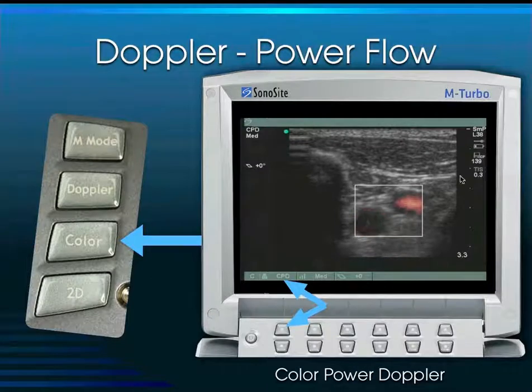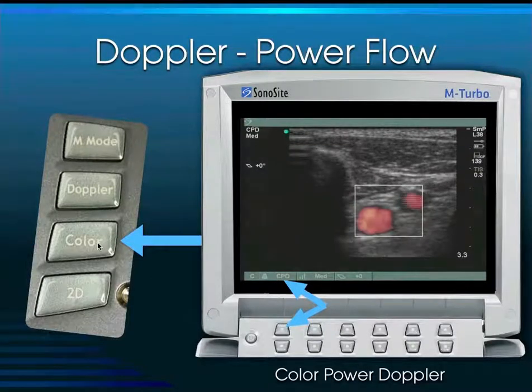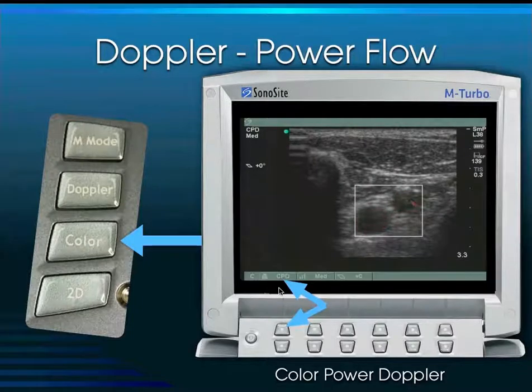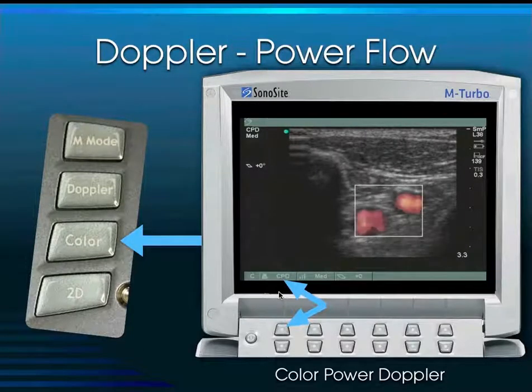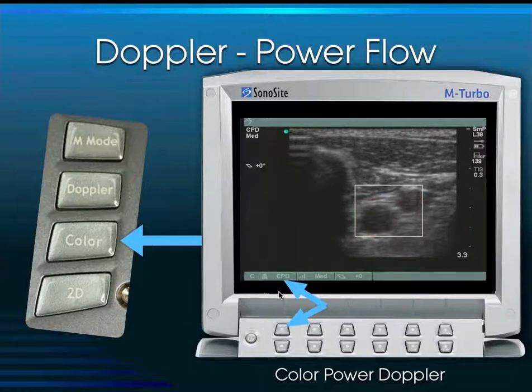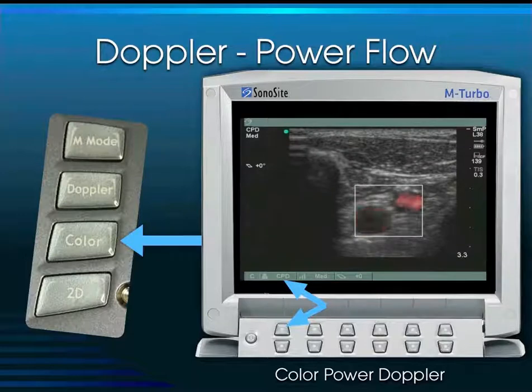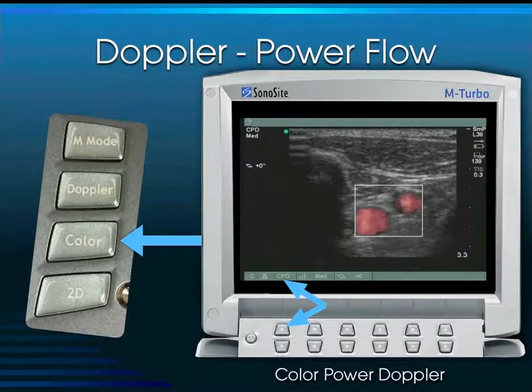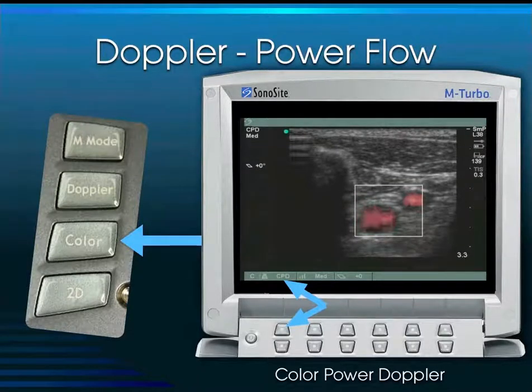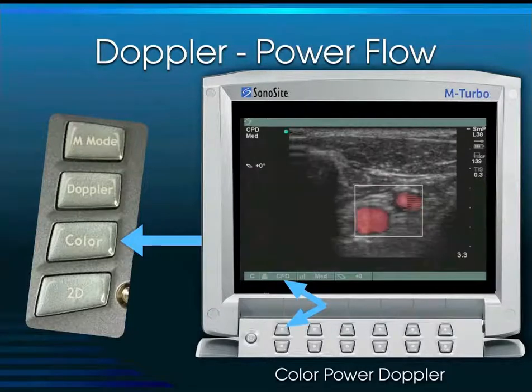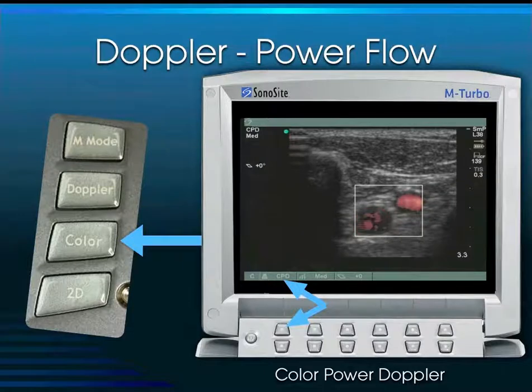You activate power Doppler by first depressing the color button, then activating it via the soft key that corresponds to the power Doppler function. This is an orange-only type of flow — it is not directional. It is a very sensitive type of flow used for identifying perfusion in tissue that has a low perfusion state, such as the testicles.